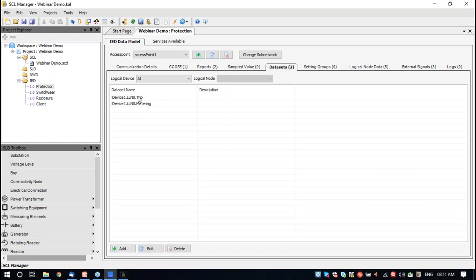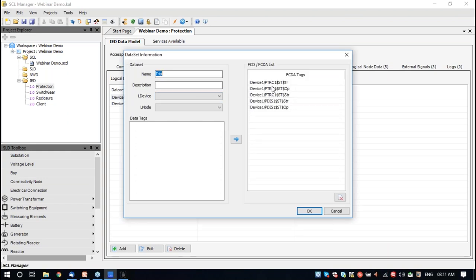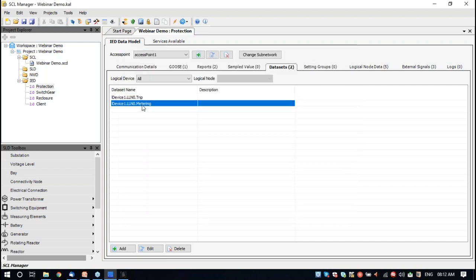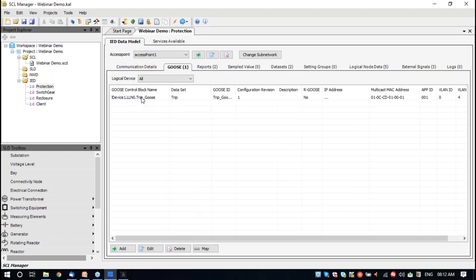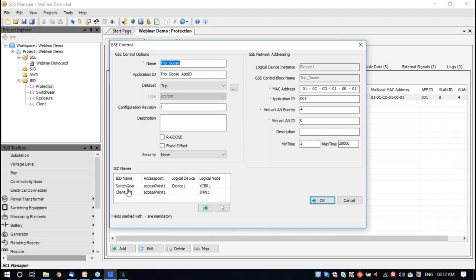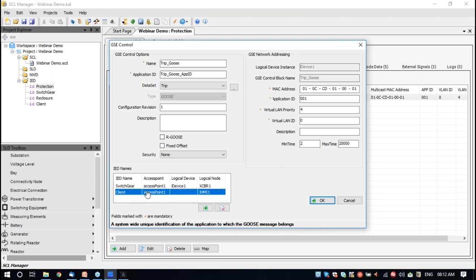We also have datasets. The first dataset is a trip signal — it will have PTRC and PDIS, which is a distance protection function. In the second dataset, we have a few metering data points including frequency, phase voltage, and current. We also have a GOOSE signal — the TRIP dataset will be sent out as a GOOSE packet. You could see that this GOOSE is going to two remote devices: the switchgear and also the client. Using this mechanism, you will know which destination IEDs are receiving a specific GOOSE signal.